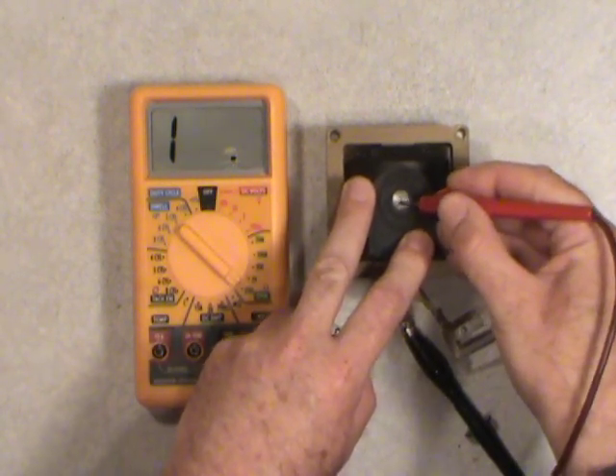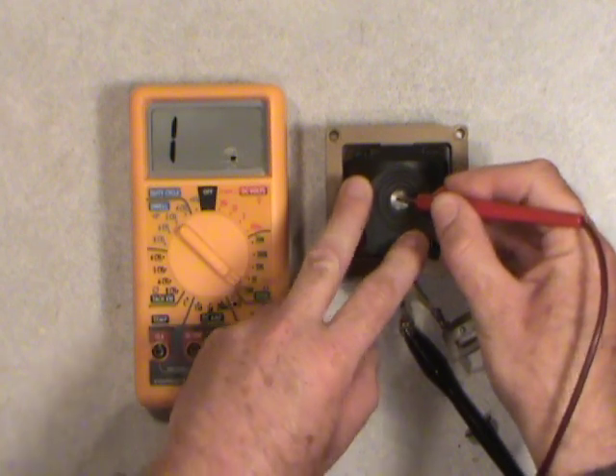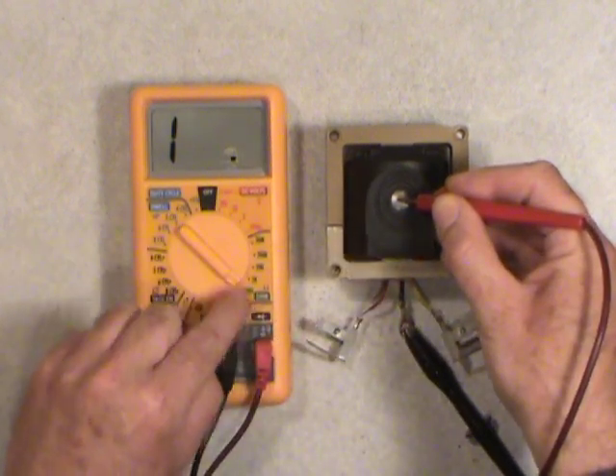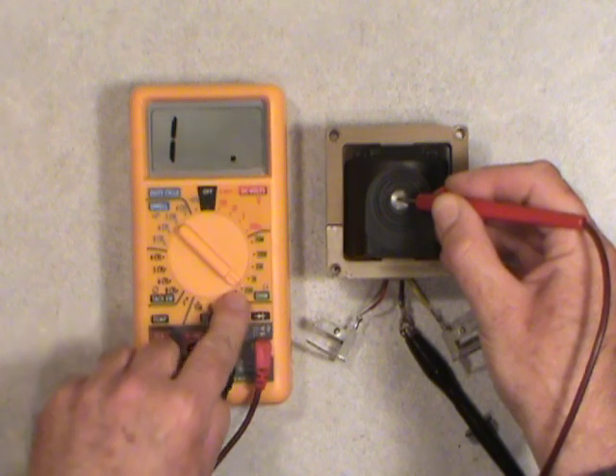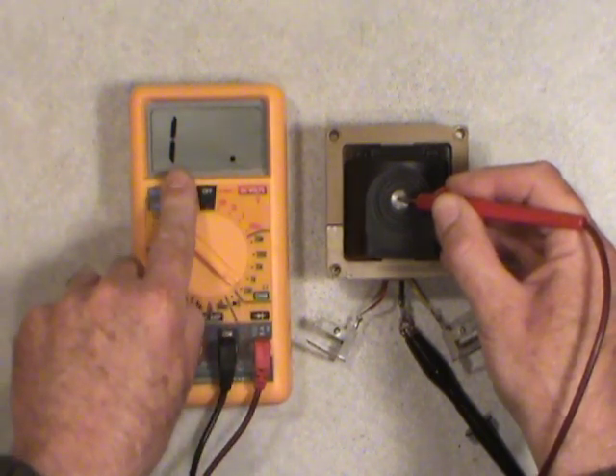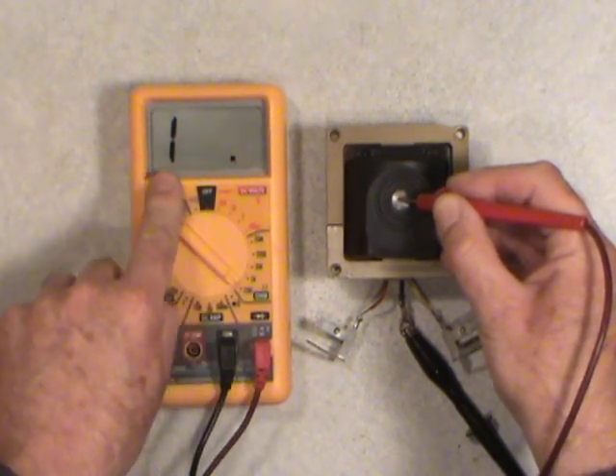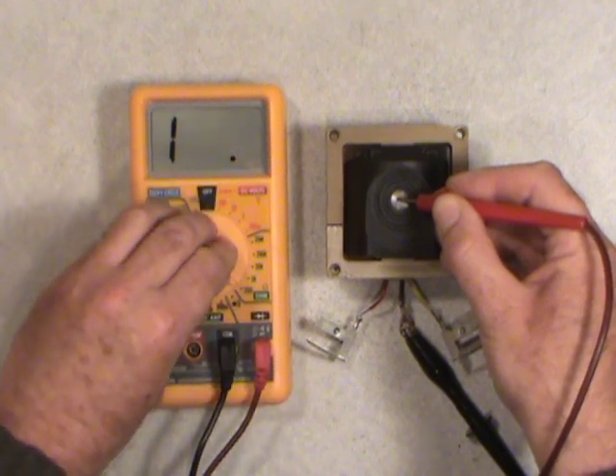Okay, scratch around, make sure it's all good, and hold pressure on it. Now the meter is set at a way too low range to get anything. If it indicates zeros or just a one, that means you're out of range, so we're going to crank it up one range at a time.